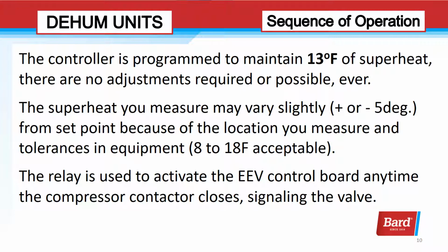The superheat you measure may vary slightly, plus or minus 5 degrees, from the set point because of the location you measure and tolerances in the equipment. So if you're going to check the superheat and you get between 8 and 18, that's acceptable.